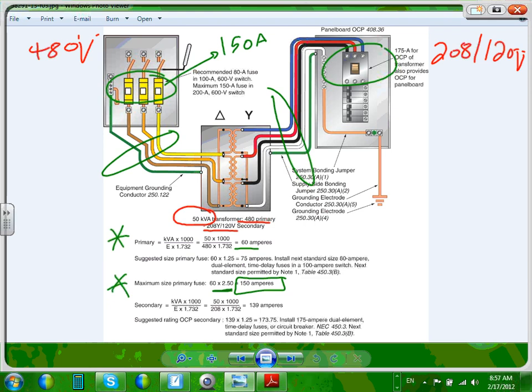Any question, guys, about primary fuse? 2.5 times 60, based on the table, equals 150 even. So the fuse is 150. Okay, the secondary fuse, if you look at what they did for the secondary, guys, the same thing, they found 139 amps on the secondary, multiplied it by 1.25 from this table, 450.3(B), and that will end up 173, and because there is a note number 1, you can go to 175. So this one here is 175.